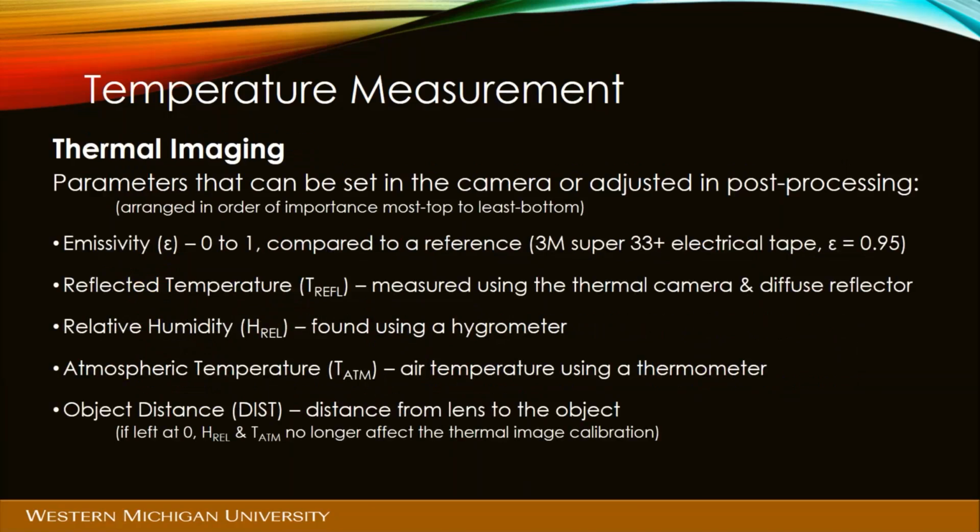The most important is emissivity, 0 to 1. And the reference we use is the electrical tape that I pulled out and showed you. The industry standard is called Super 33. Or you can do Super 88, the thicker, heavy one. They're the same surface, they both have an emissivity of 0.95. So that's what we can use for our standard in order to figure out the emissivity of basically any material surface in the world.